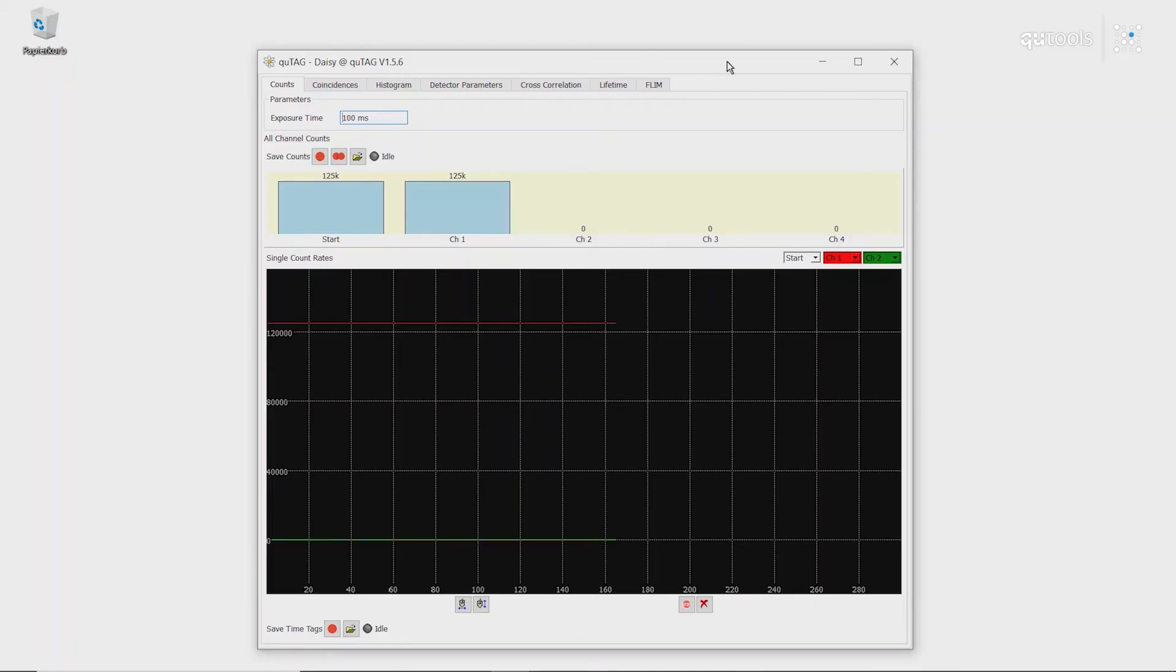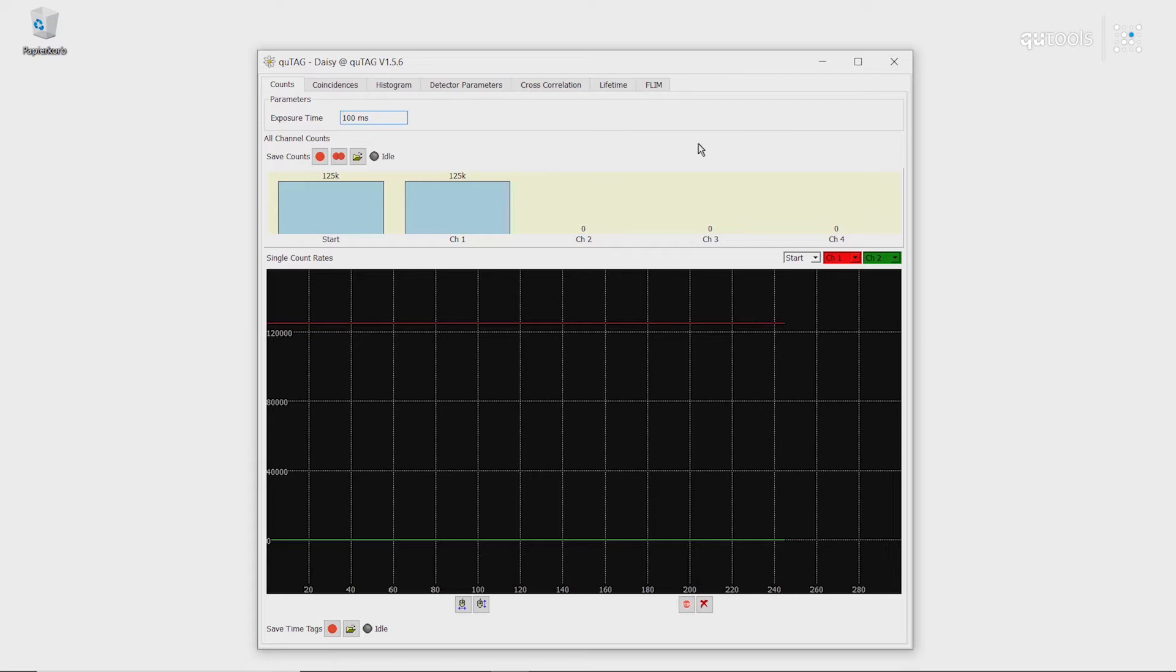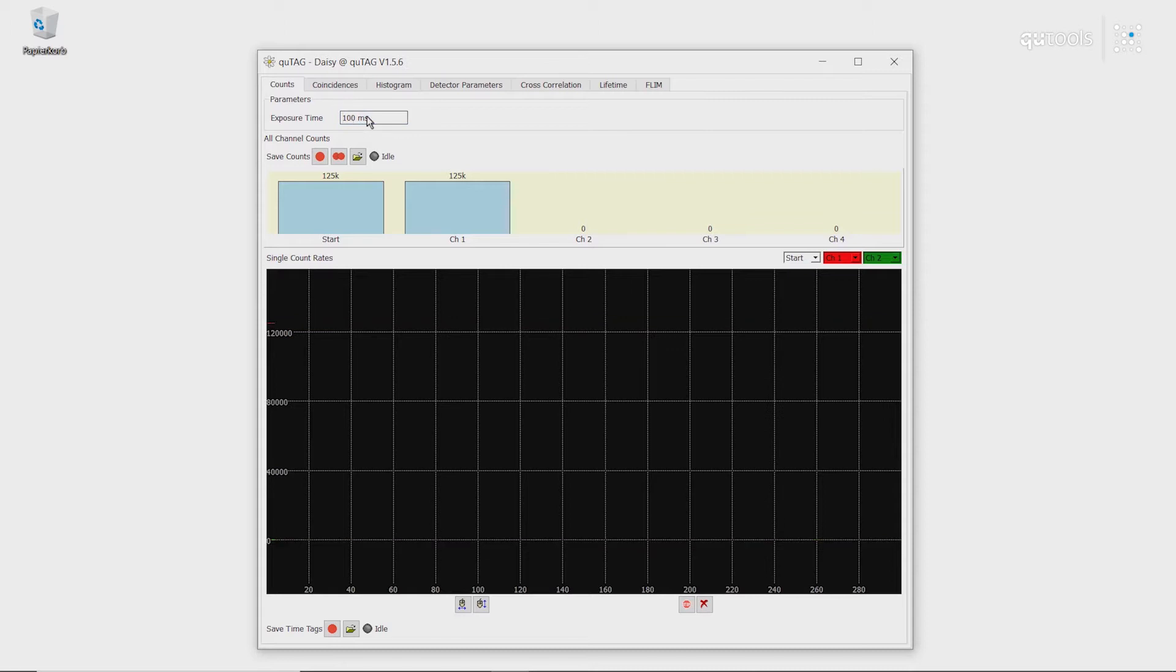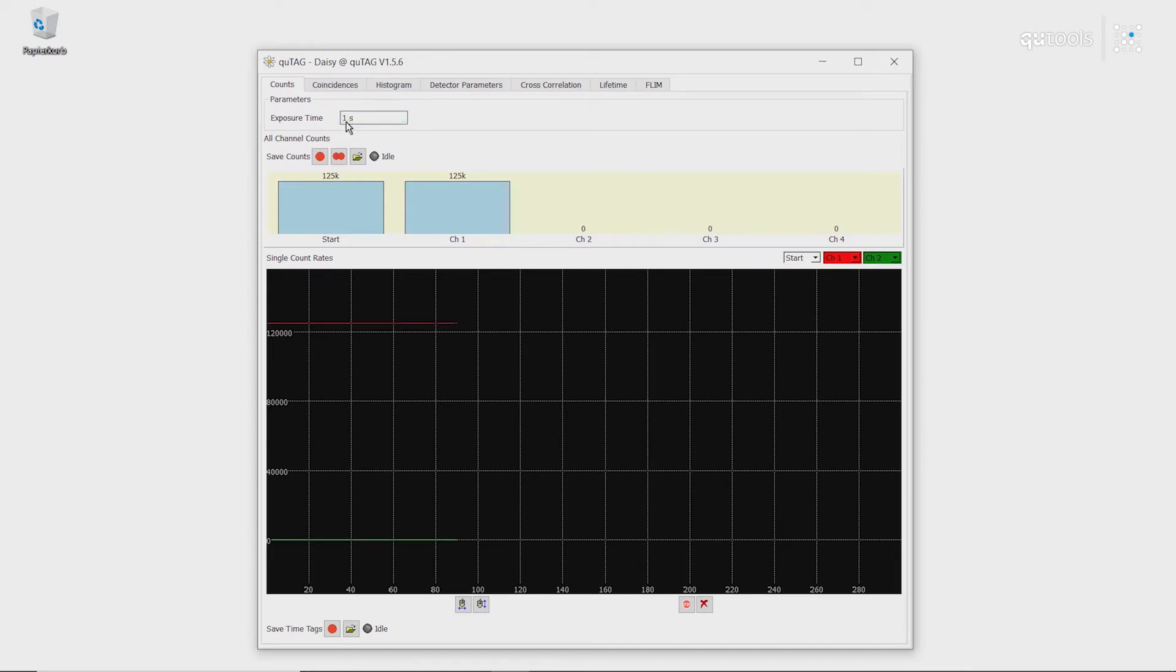This is the proprietary software that we use to interface with our quTAG, which is called DAISY. In this interface here, we are shown the number of counts present on all channels per exposure time, which is currently set to 100 milliseconds. If we want, we can change the exposure time, for example, to 1 second, and all the numbers update correspondingly.